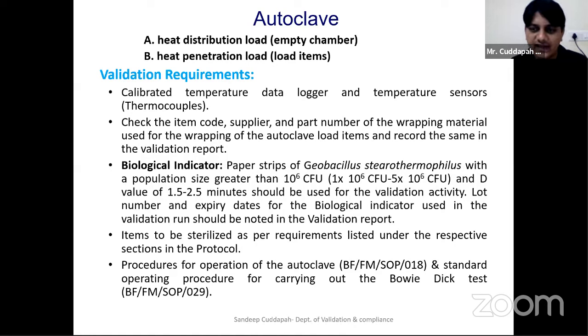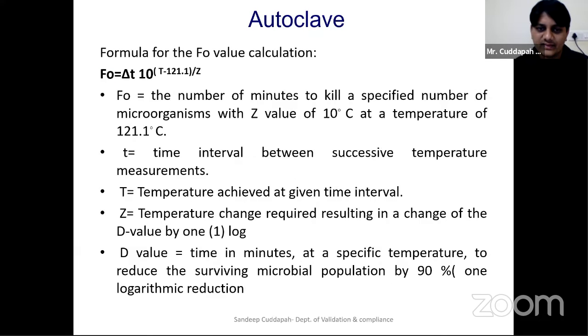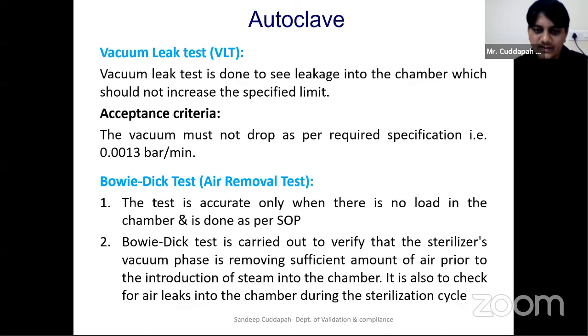If you see sterilization, you will verify by placing a biological indicator, and you will place some external thermocouples or sensors to verify whether the equipment is reaching that temperature, and whether the biological spores are killed with your defined recipe set parameters. You will verify this during qualification. These are some formulas to calculate the lethality, and you will get this even in guidelines. These are additional processes which you will do to make sure the equipment is performing consistently.